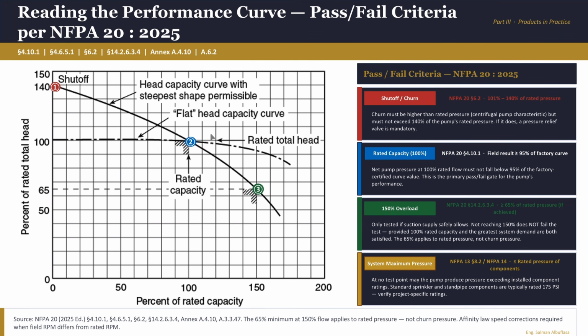Criteria 2, moving on to the middle, the rated capacity. This is the pump identity, the number on its nameplate. If you bought a pump rated at 1000 GPM and 100 PSI, this is the point where it must prove it. Now we're pushing it one more push. Far right, overload. This simulates a large fire with many sprinklers open at the same time. Pressure will definitely drop. Expected, and it's acceptable. It's normal. But it must not collapse. And it must hold 65% of its rated pressure.